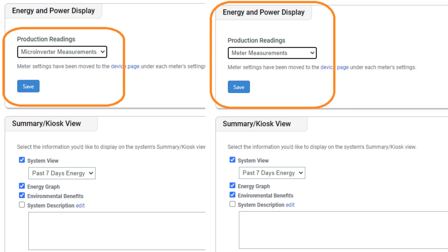If meter measurements are displayed in the production readings drop-down and you are not using a physical meter, choose microinverter measurements and then click Save. Remember, if you intend to measure consumption data, you must have this set to meter measurements and have physical meters for both production and consumption installed at the site.